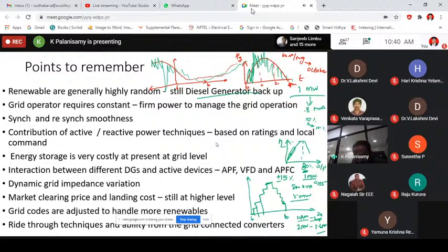So when I am injecting reactive power or absorbing reactive power from the grid, accordingly my active power must be reduced. So I am losing profit. All those things are there when you are operating grid connected, right? The amount of active or reactive power supplied to the grid or absorbed from the grid is based on the rating of your device, the rating of your plant. It means if you have 1 megawatt, based on the frequency high or low or voltage high or low, you may be allowed to have 10%, 15%, right?